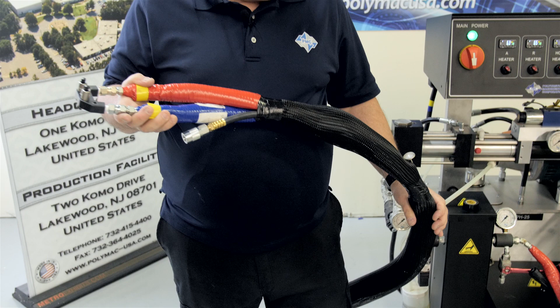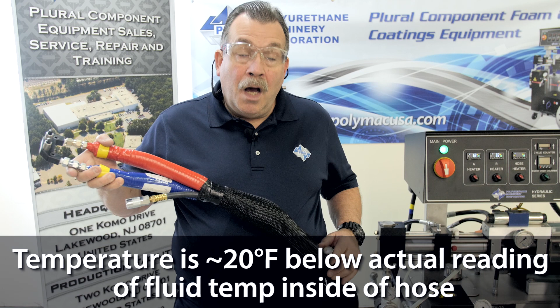One thing to always keep in mind is that the temperature reading on this thermometer is approximately 20 degrees below what the actual fluid temperature is inside the hose. So if I need 120 degrees to spray with, I want to see 100 degrees on this thermometer.